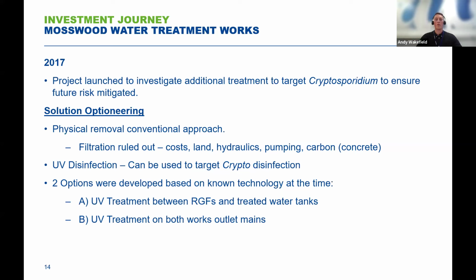The raw reservoir gravitates into the works, and the majority of the treatment is through gravitational flow, with the Durham system only being pumped into supply. If we were to do this, it would completely change the hydraulics of the site, and there would be a lot more interstage pumping and the associated costs and energy consumption with that. There would also be increases in carbon, particularly through the construction of the additional stage.